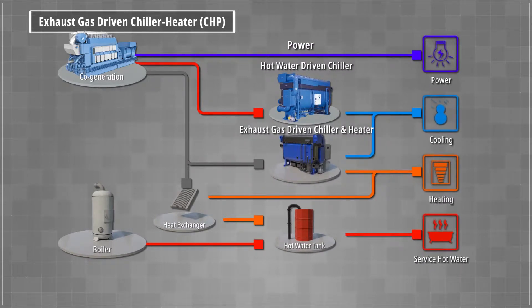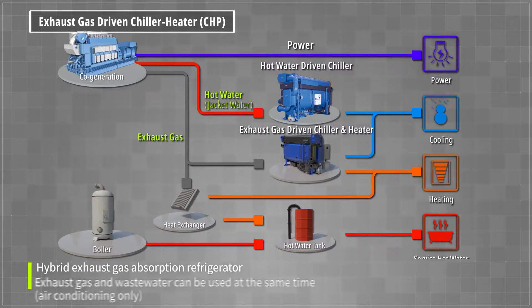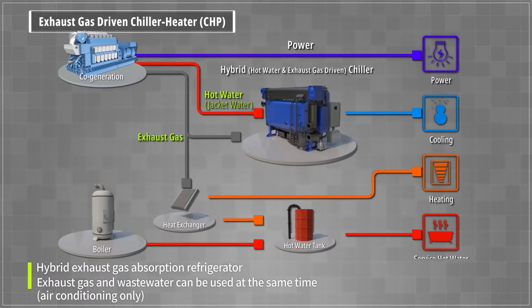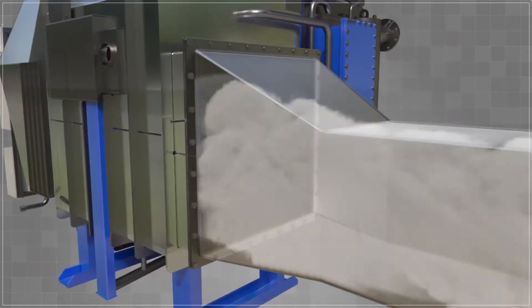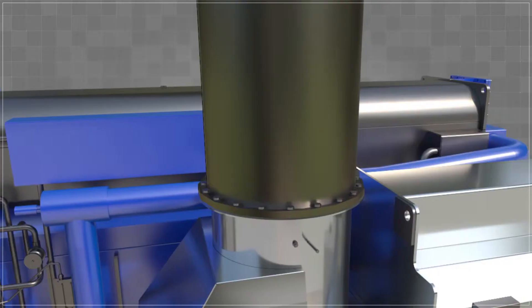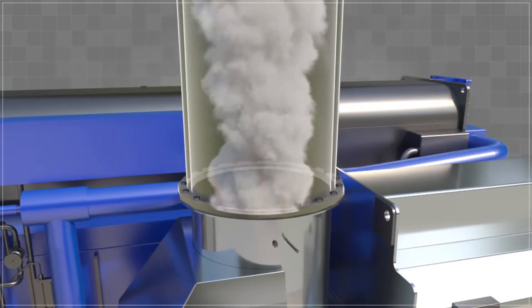CHP utilizes exhaust gas waste heat to provide chilled and hot water, while HWARL utilizes engine jacket water to provide chilled water. The CHP model, a hybrid type absorption chiller, can use a combination of engine exhaust gas and cooling water as a heat source.